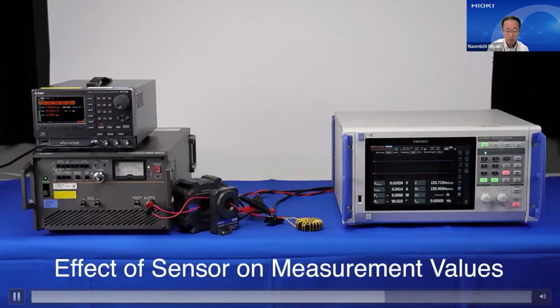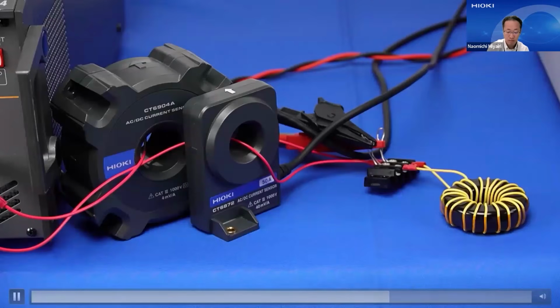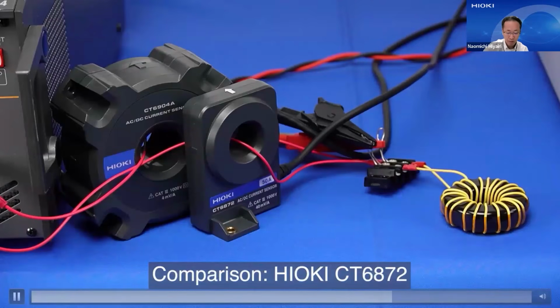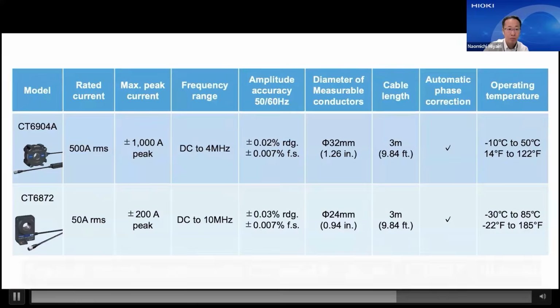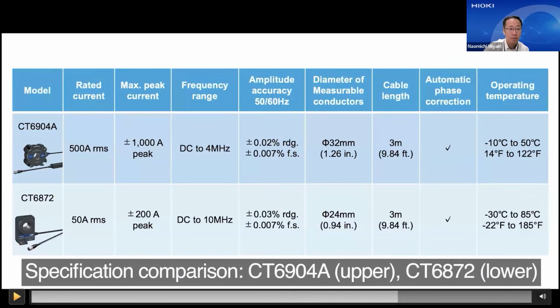So next, we are going to see the impact of the current sensor on measurements. For comparison, we are using the CT6872. This is each sensor's specification. CT6904A is a 500 amp current sensor, and the frequency ranges from DC to 4 megahertz.